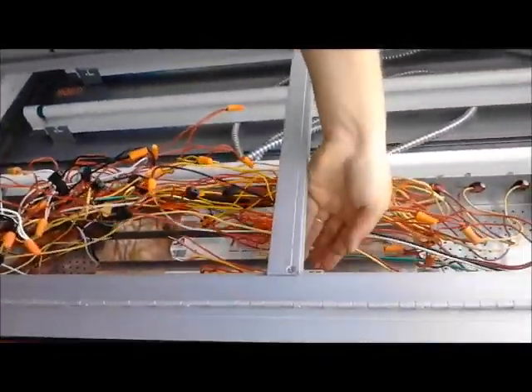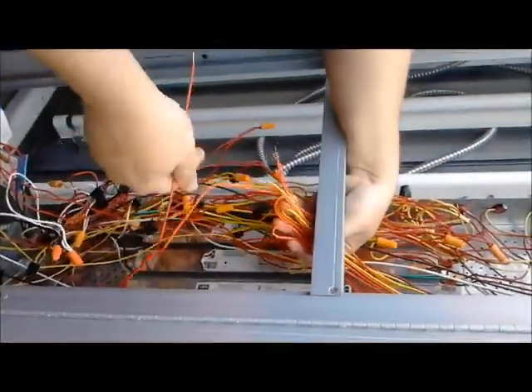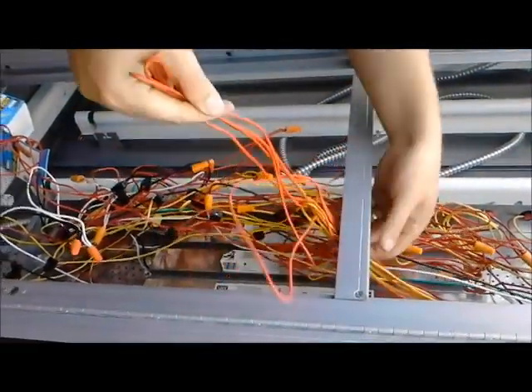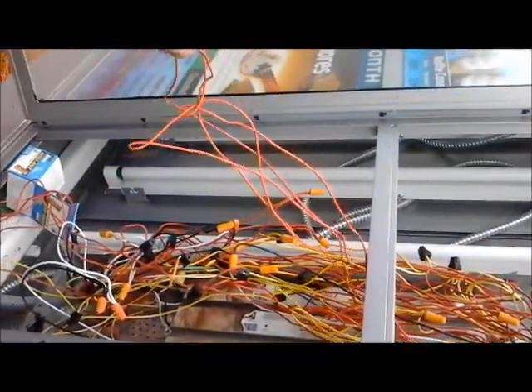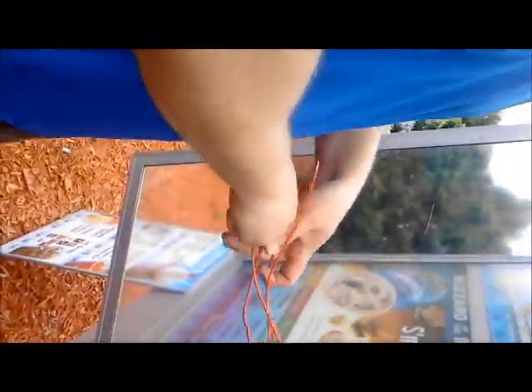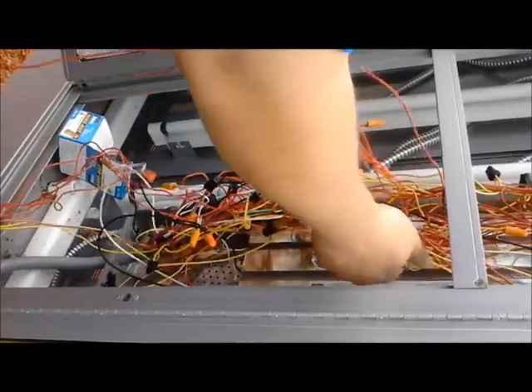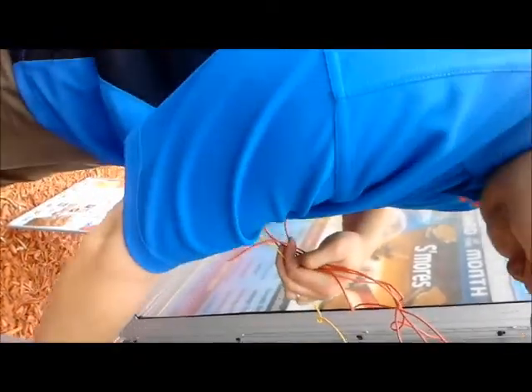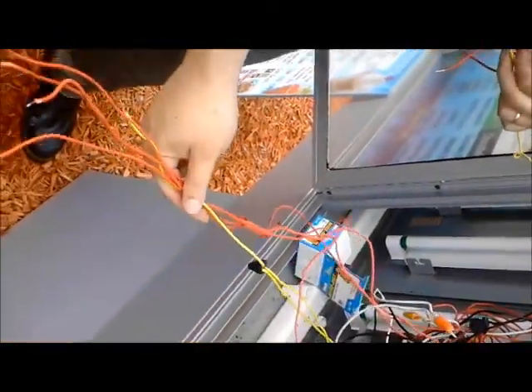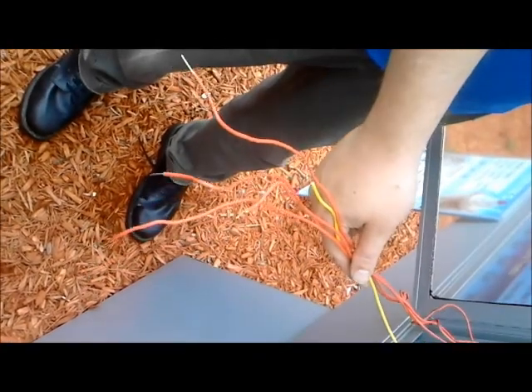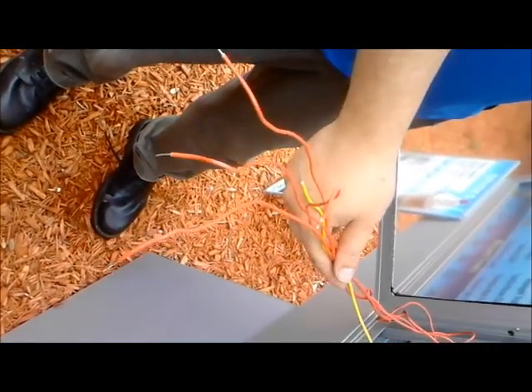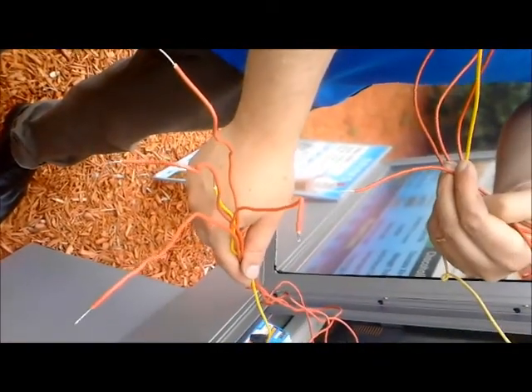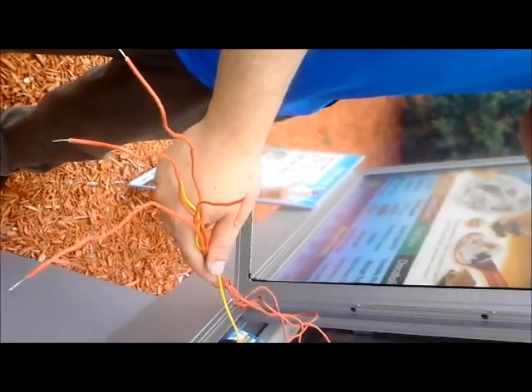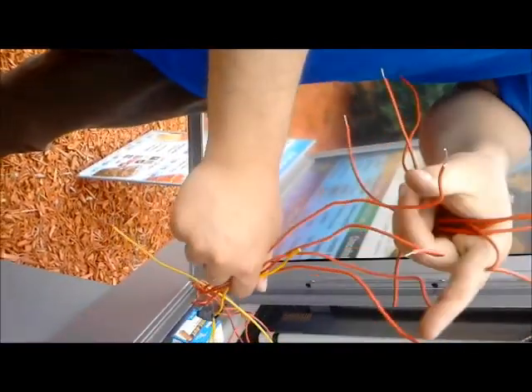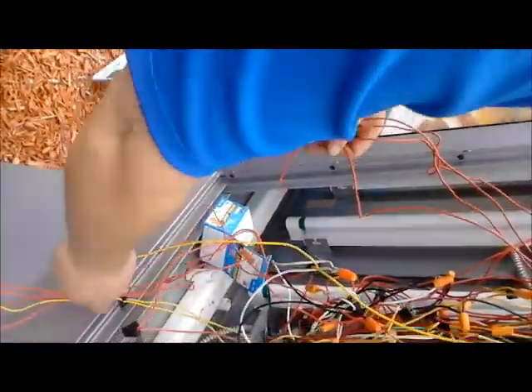Now, the red and yellow wiring on the ballast, you want to stretch this out. Remember, this stuff is coming from the top, so it's very easy. You shouldn't be too likely to cross connect here, since everything on top is from the ballast, and all the wiring down here on the bottom is from the menu board. Which red goes to which red is not a big deal. It's just don't connect the menu board to the menu board or the ballast to the ballast. You want to make sure these four red go to those four red and don't cross connect them like this.